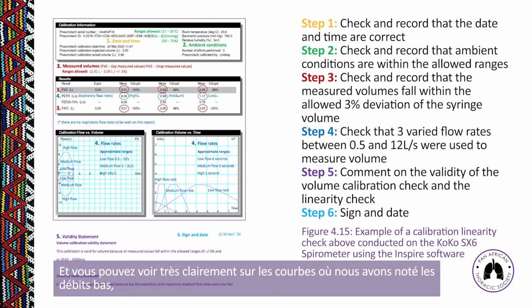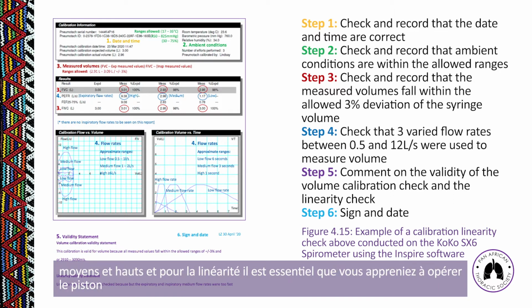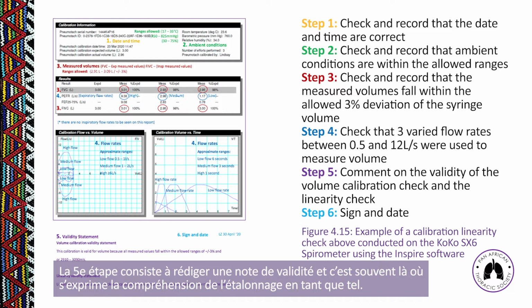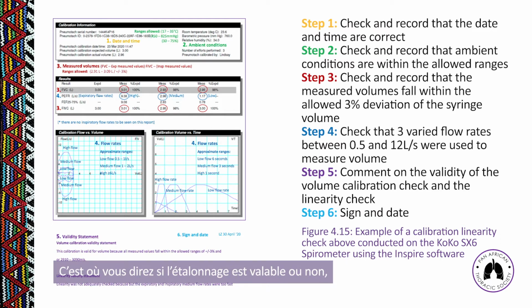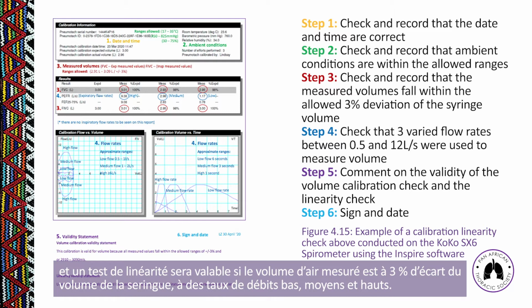So you can see on the graphs very clearly where we've documented low, medium, and high flow. And in linearity, it's very, very important that you learn to pump that syringe handle at the different flow rates so that we can measure volume across the range. Step number 5 is writing a validity statement, and this is often where the understanding comes of calibration itself. So what you want to say is whether the linearity check is valid or invalid. A linearity check is valid if the volume of air measured is within 3% of the syringe volume at low, medium, and high flow rates.